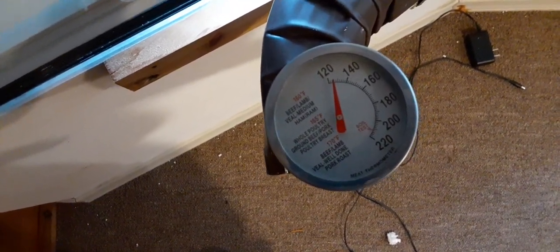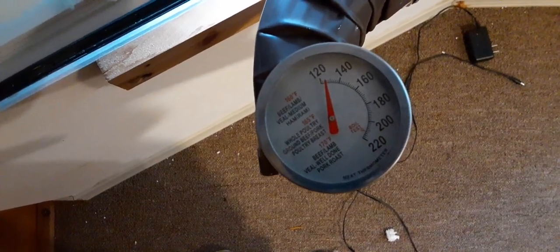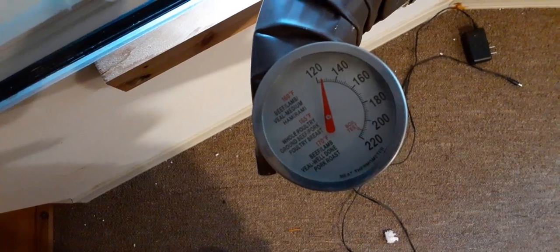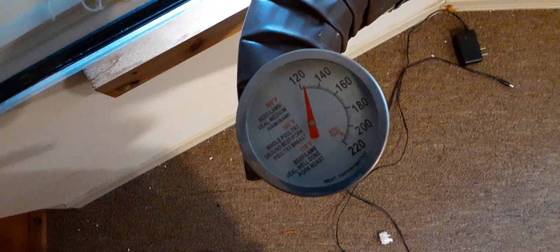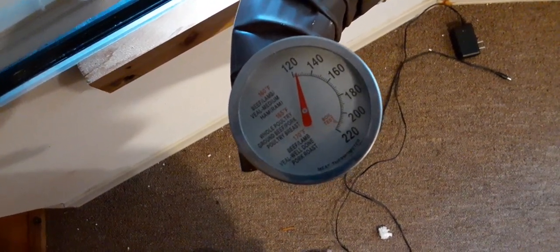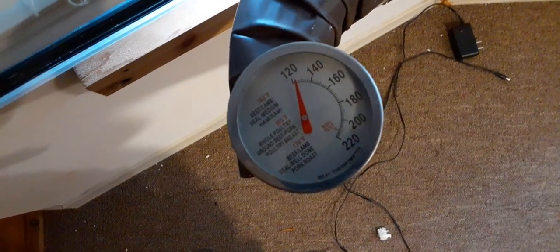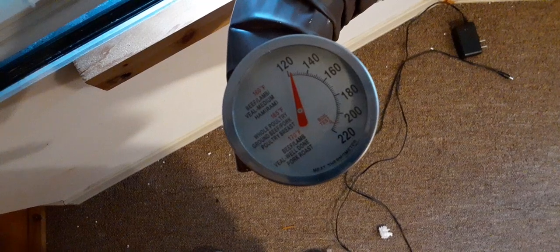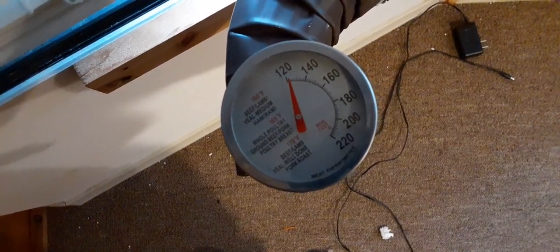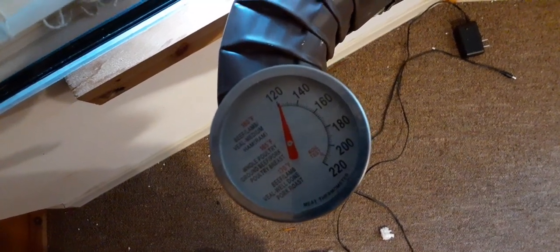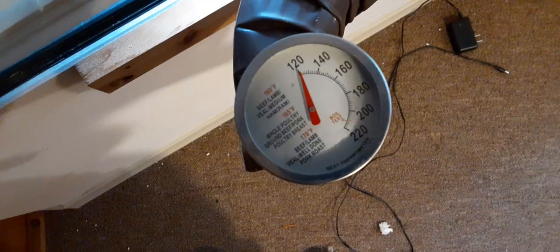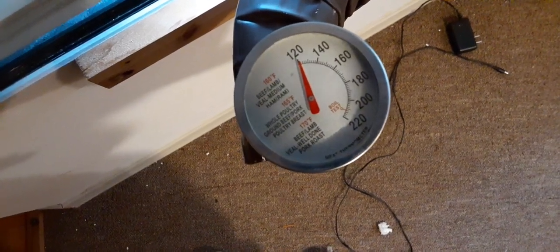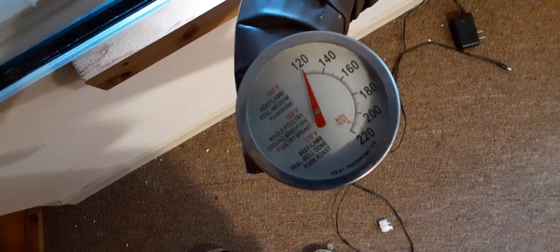Now what's going to happen is it's going to start going down. I'm going to hold here until it starts declining, which shouldn't take long. There you go, there goes the descent. Now you can see it moving toward the 120. You can see now we're back down to 120. That shows what I needed it to show—there's going to be a decrease in the temperature as that exhaust pipe starts pulling.